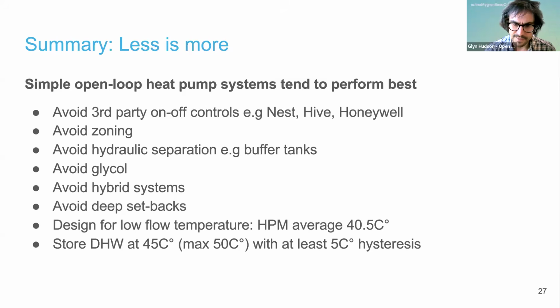Design for the lowest flow temperature possible. The systems on HeatPumpMonitor averaged a design flow temperature of 40.5 degrees, but many of them are running lower than that. Aim to store hot water at about 45 degrees, maximum 50, with at least 5 degrees hysteresis.